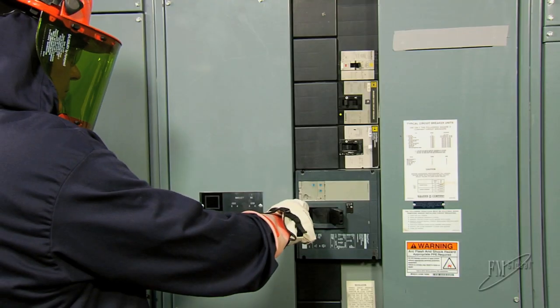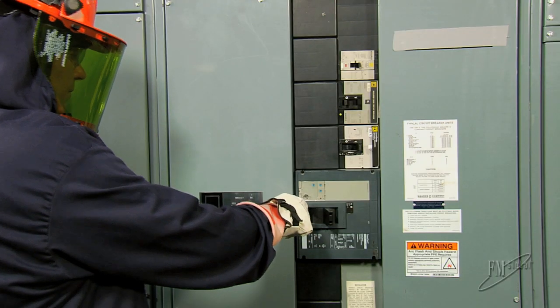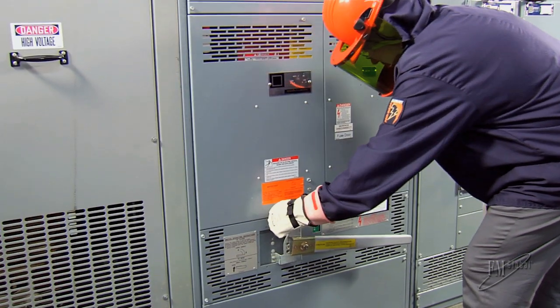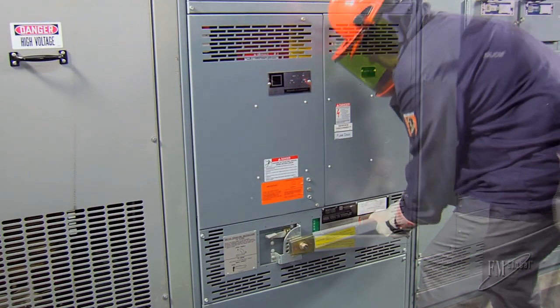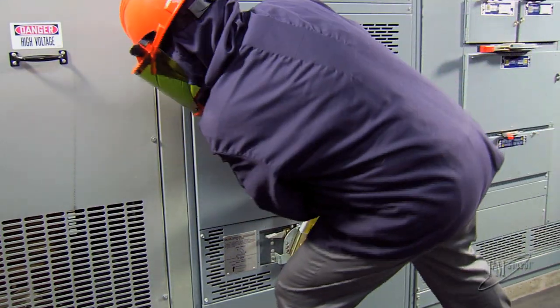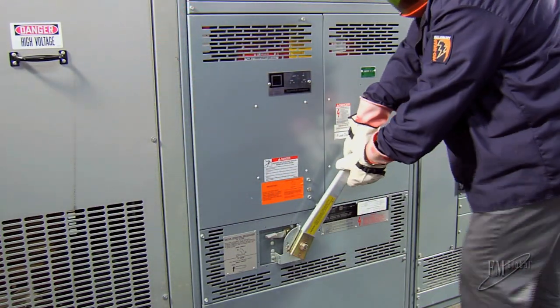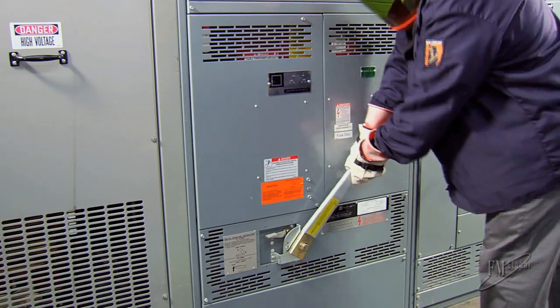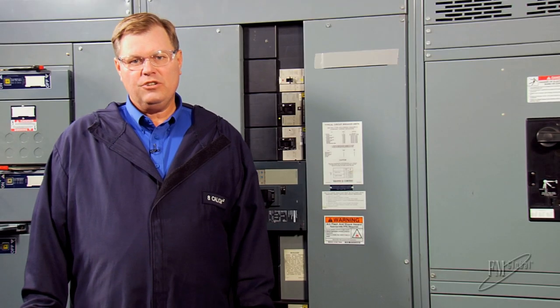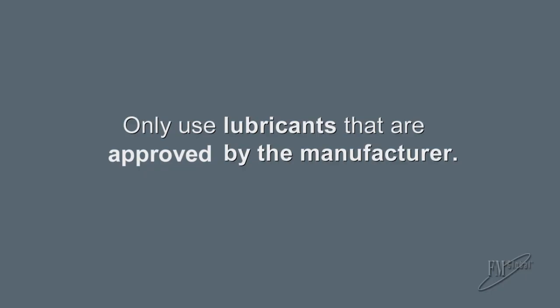We also recommend that all breakers be exercised at least once a year to ensure that they will open and close when needed and that any deficiencies are identified and corrected. Some breakers also require lubrication. Remember, only use lubricants approved by the manufacturer.